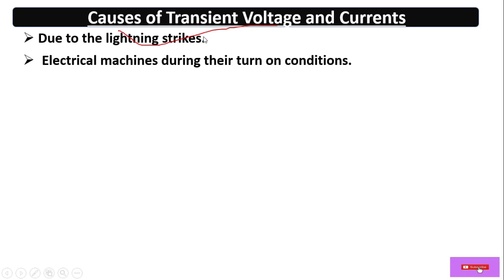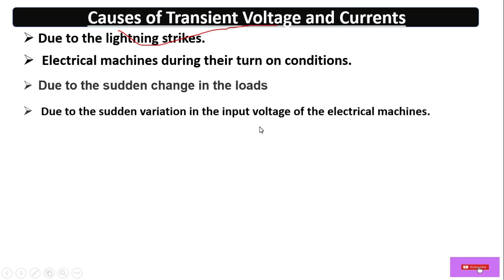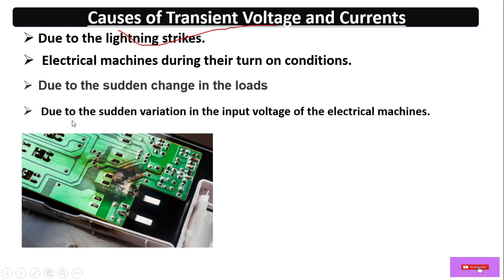The causes of transient voltage and surge current include: lightning strikes, switching of electrical machines during turn-on, or sudden changes in loads. For example, if we suddenly increase load from 20 kilowatts to 200 kilowatts within a millisecond on a particular feeder, transient voltage or surge current may arise. Sudden variation in the input voltage of electrical machines can also cause transient voltage and surge current.